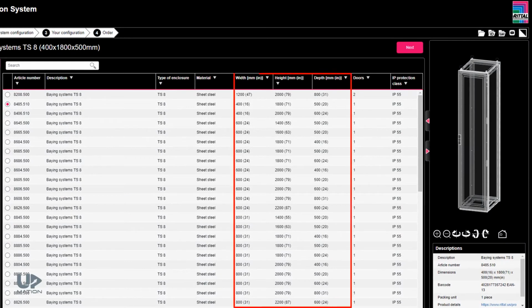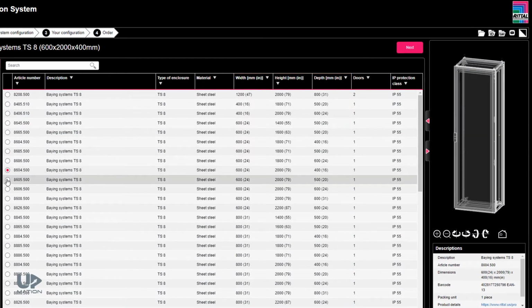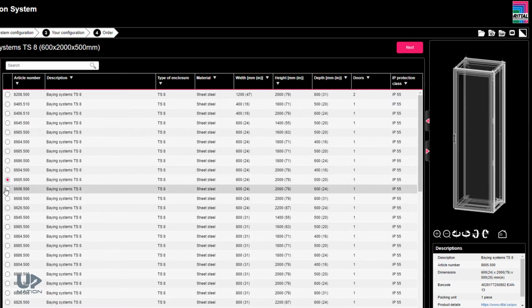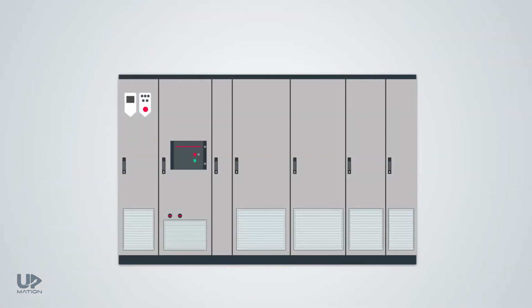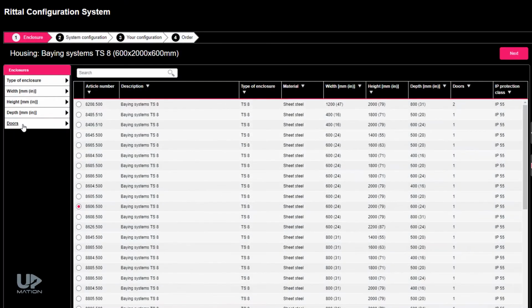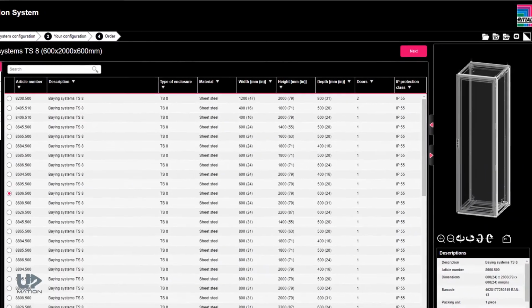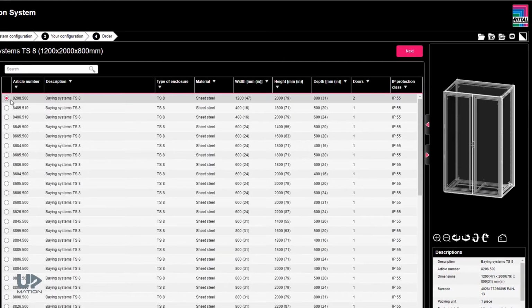Generally, there are standard dimensions for the industrial panel enclosures that we can choose among when we are designing our electrical panel. However, you might see some custom size enclosures in particular applications, such as these freestanding VFD or variable frequency drive panels. We can also choose 1-door or 2-door panels depending on the width of the panel and our desire.